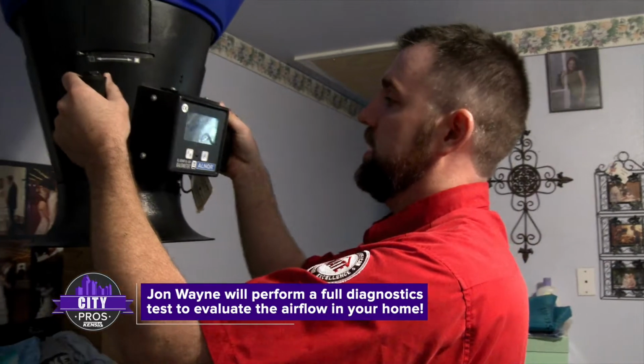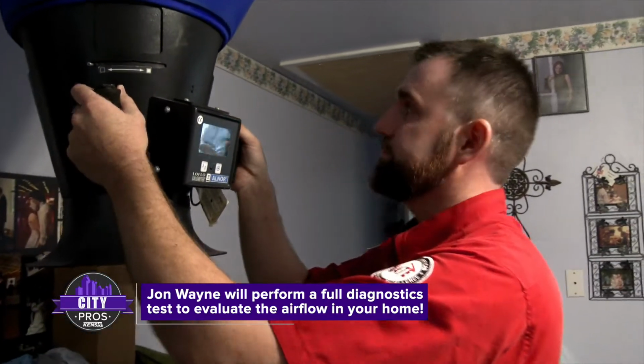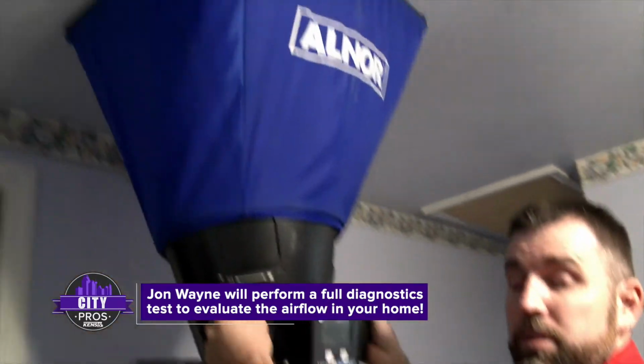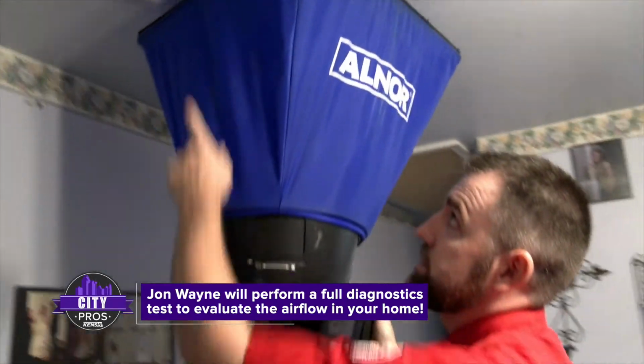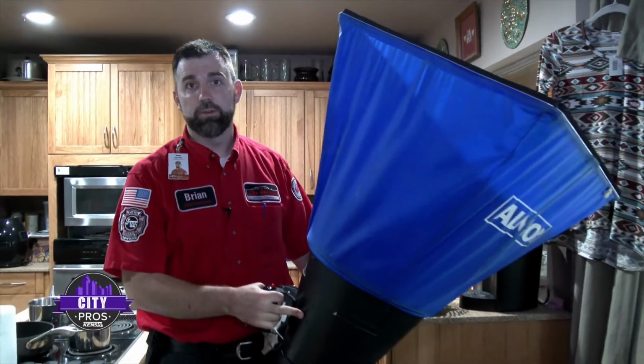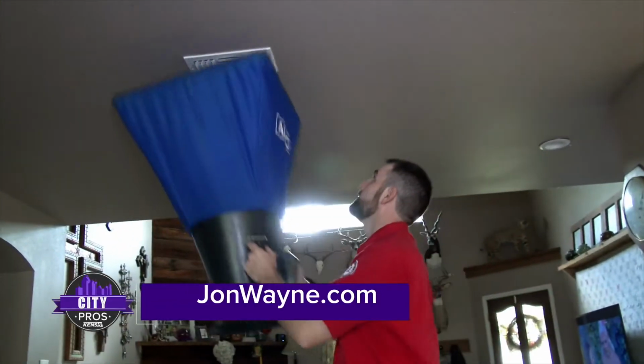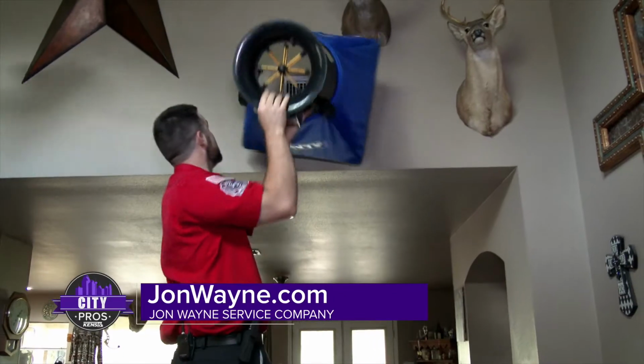Right now we're going to check the airflow in the problem room. This is called a flow hood. It's going to measure how much airflow is actually coming out of our vent here. It's very important that we check each room, not just the problem room. We want to look at each room individually and then the house as a whole.